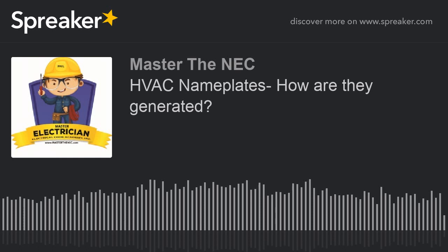And so that's what the topic of today's episode is. We're going to talk a little bit about that because I want to remove the confusion that people have about how to apply the applications in G. So, if you've got your code book, we're in the 2017 National Electrical Code. You go to 240.4(D), you see small conductors. And then again, it says, unless specifically permitted in 240.4(E) or (G). And of course, when we get to G, you'll see that it is specifically permitted for what our application is that we're going to talk about, which is an outside air conditioning unit.